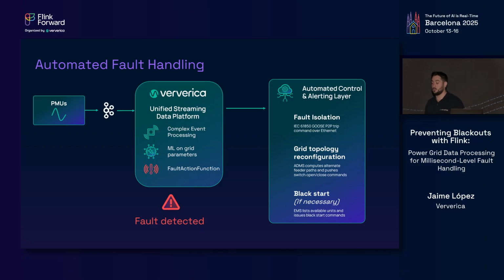If everything goes to hell, you can also start thinking about black start. In the end, the only way to come out of a blackout is to start some generation that doesn't need to be connected to the grid to start up. So this is also planned by the TSO. You can already issue a black start command so that, let's say, a town goes black. There's going to be a generator that's going to patch it up and bring it back online before that spreads to the neighboring town, neighboring province, neighboring country.